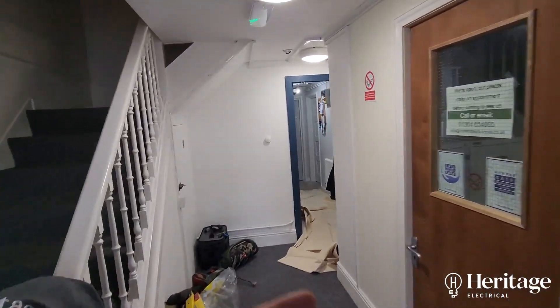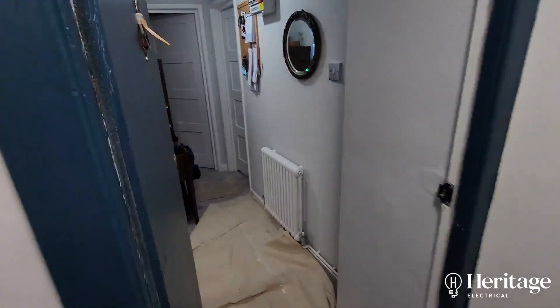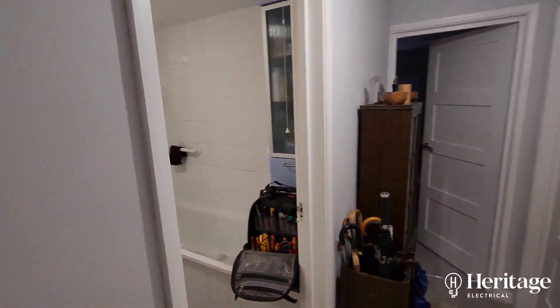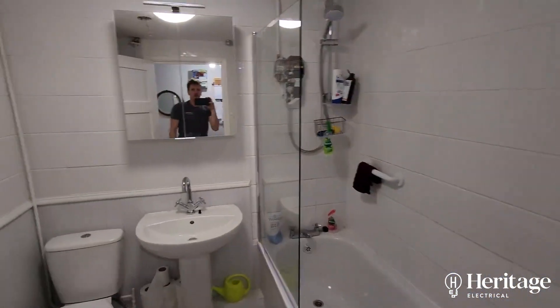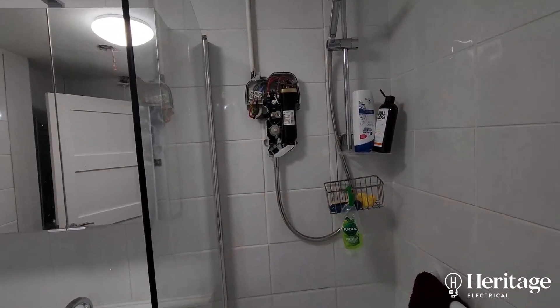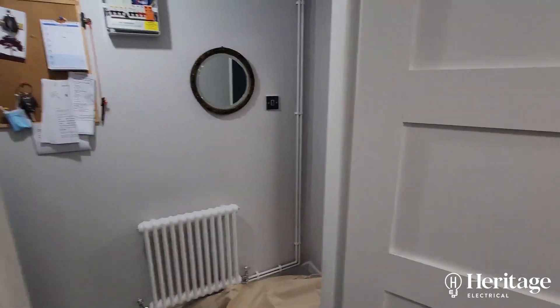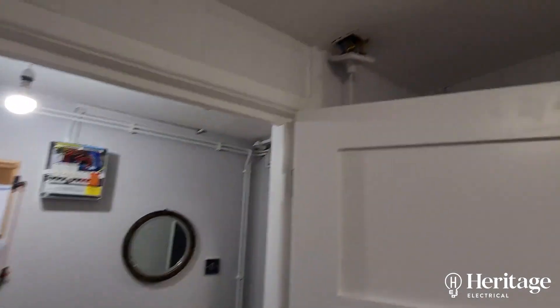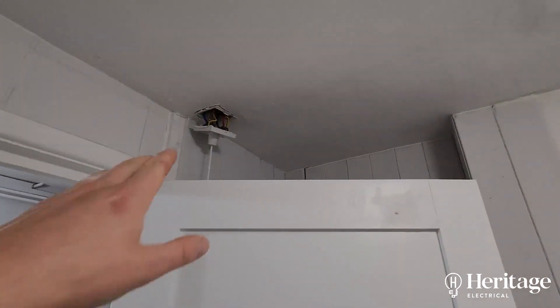He's got an 8.5 kilowatt shower in here. If he's got a cooker on, washer, and electric shower, he could quite easily go over that 45 amps - the shower is probably drawing near 40 amps itself. With some other stuff on, you could push that 45-amp supply past it.